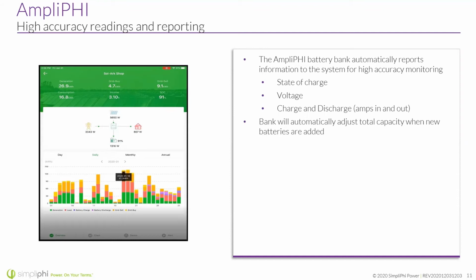The AmpliPhi battery bank automatically reports information to the system for high accuracy monitoring, including state of charge read directly from the battery, voltage, and charge and discharge amps in and out. We used to rely on what the system itself could tell, maybe through a shunt or reading its own multimeter voltage coming through. In this case, the battery takes that data directly from itself and reports it to the system.